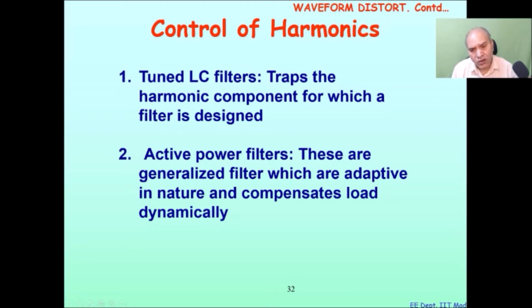Active power filters are the modern solutions for filtering the harmonics, and as the name indicates, they consist of active power devices, mostly power electronic switches. The building blocks of active power filters are therefore power converters, voltage source inverter, current source inverter. So these converters form the heart of the active power filters. These are generalized filters, adaptive in nature, and they compensate the load dynamically. You need not have a separate filter for each frequency because it is adaptive and generalized in nature, so if it is of proper rating, it can compensate all the harmonics alone.